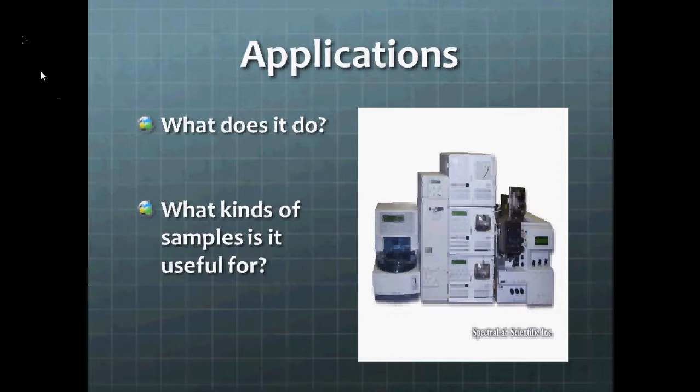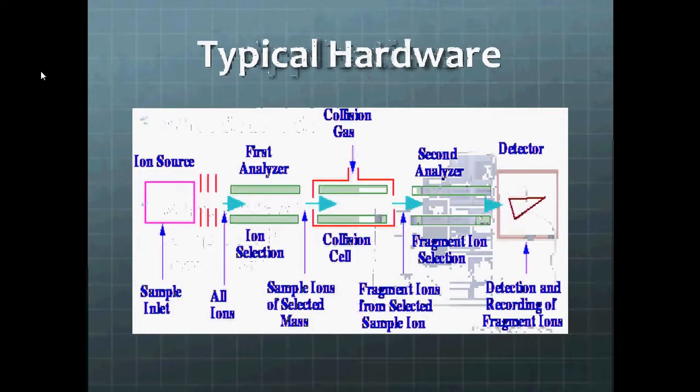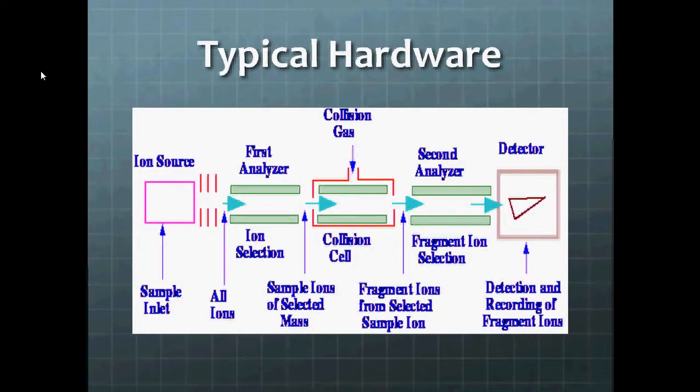Here's the typical hardware layout for a triple quadrupole. First, your sample enters through the sample inlet. This can either be done through a direct injection or coming out of a separation method, and it'll enter the ion source, which is usually electron impact but can be a lot of other things. These ions leave the ion source and are accelerated through the first quadrupole, which filters them according to their mass charge ratio.